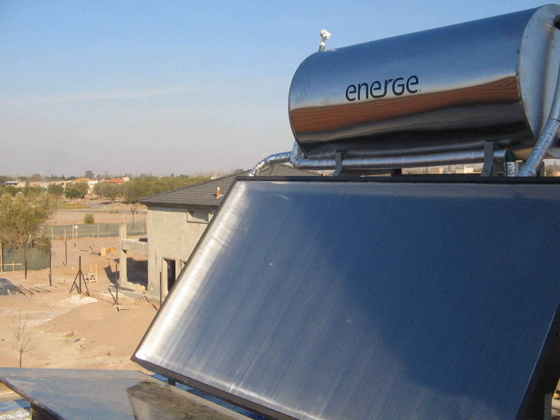Evaporation ponds represent one of the largest commercial applications of solar energy in use today. Unglazed transpired collectors are perforated sun-facing walls used for preheating ventilation air. Transpired collectors can also be roof-mounted for year-round use and can raise the incoming air temperature up to 22 degrees Celsius and deliver outlet temperatures of 45 to 60 degrees Celsius. The short payback period of transpired collectors makes them a more cost-effective alternative to glazed collection systems. As of 2015, over 4,000 systems with a combined collector area of 500,000 m² had been installed worldwide.